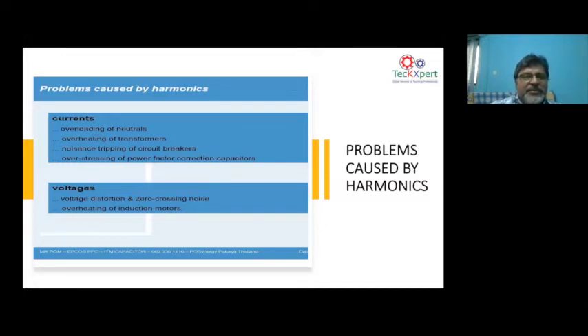Breaker tripping, naturally, as I said before: if some phenomenon happens by a non-steady state resonance, it can end up in the tripping of a breaker. Or tripping can be due to any other non-steady state phenomena, as I explained about power quality itself. Your capacitor banks will get stressed because the impedance equation is 1 by 2 pi FC. So the higher the harmonics, the lower the impedance, the higher the overloading. So you're stressing the capacitor a lot if you don't correctly design the capacitor bank in the environment of harmonics.